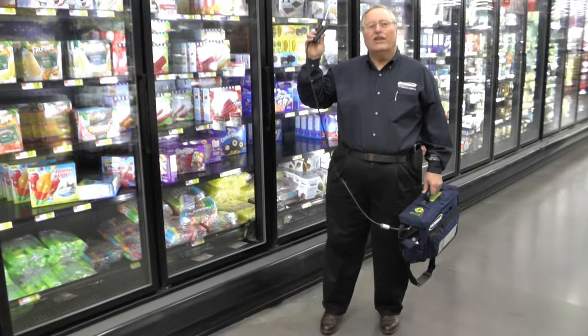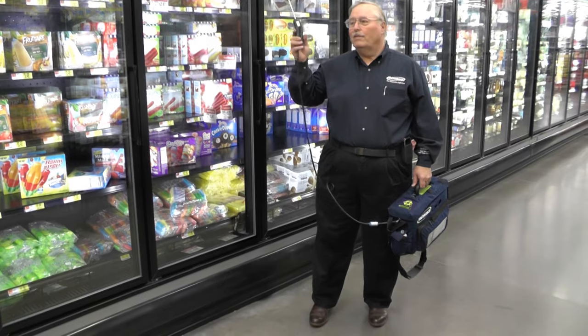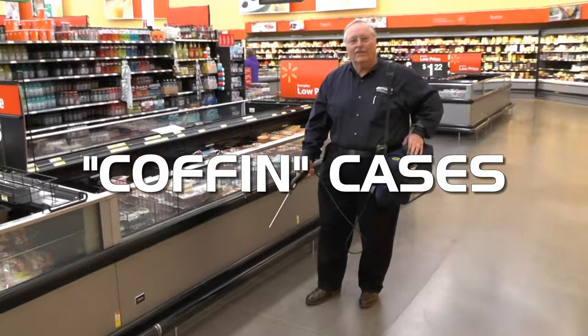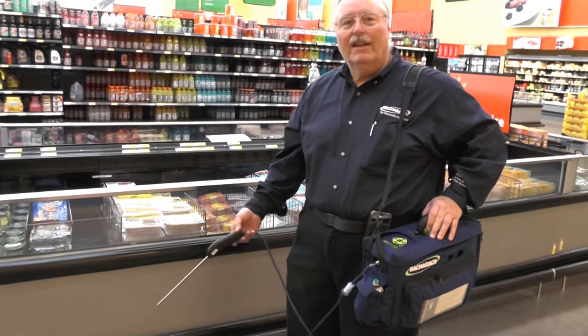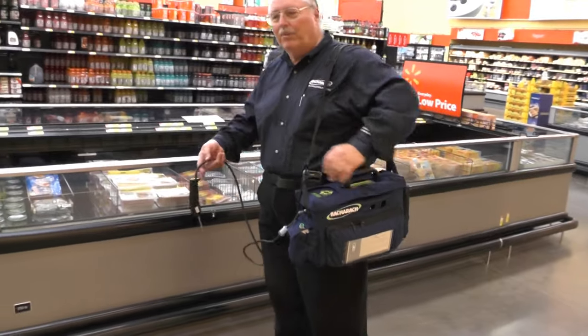It may be just a coincidence, but this is one area you want to check very closely when you start getting leaks picked up in these cases. Testing on coffin cases actually needs to be done in two places. Since these are fed by a pit underneath the unit, one of the best ways to start is to troll around the outside of it with your probe.